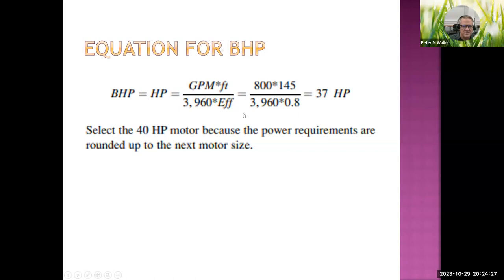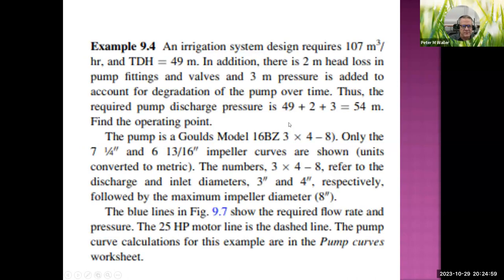The brake horsepower equation in Imperial units is: BHP = (gallons per minute × feet of head) / (3960 × efficiency). For the previous example: 800 gpm × 145 feet / (3960 × 0.80 efficiency) = 37 horsepower.